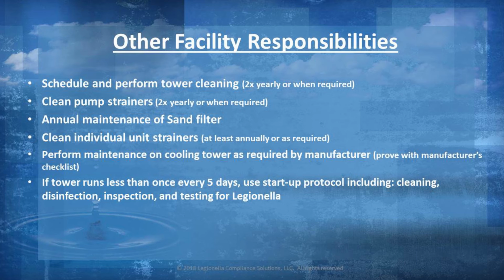The responsible person must also schedule and perform tower cleanings at least twice a year and whenever required. You also should clean the pump strainers every time a cleaning of a cooling tower is performed, if not more frequently. The facility responsibility person must also conduct annual maintenance on sand filters, disc filters, cyclone separators, and any type of filters in the system. If your system is of package unit design, you must clean individual unit strainers annually or as required. You must perform annual maintenance on the cooling tower required by the manufacturer. You should prove this by filling out the cooling tower maintenance checklist.